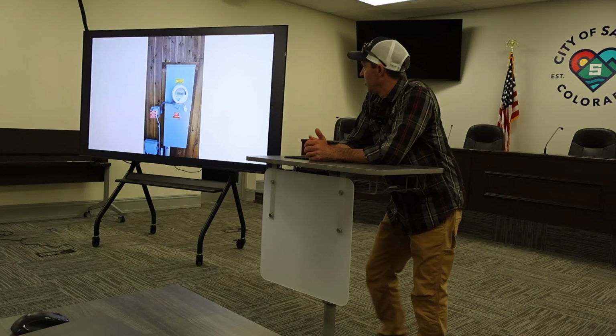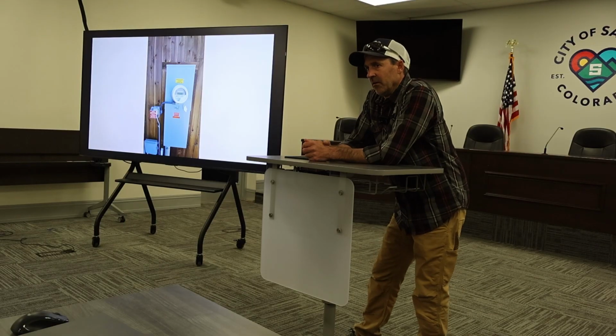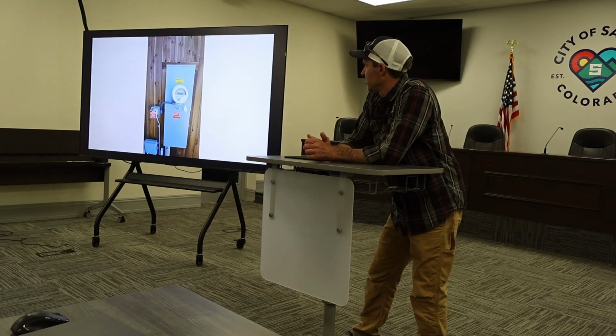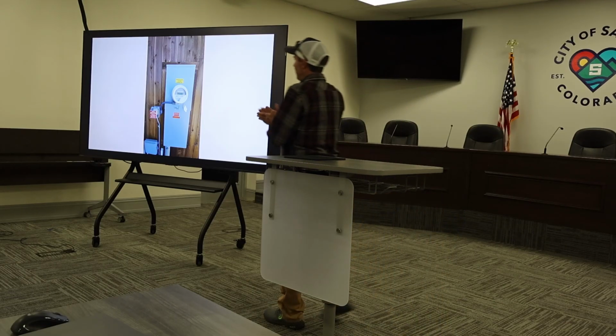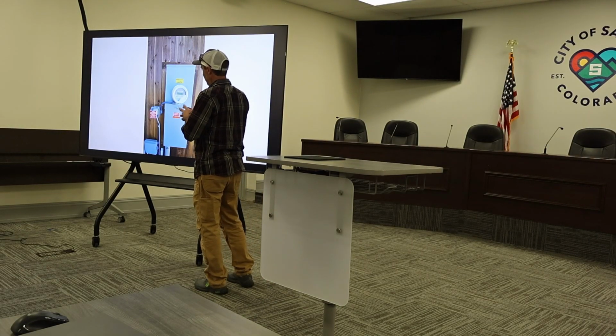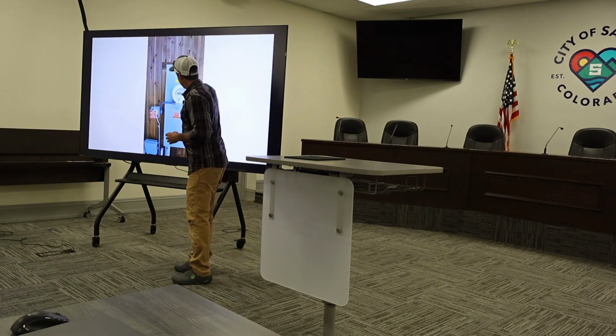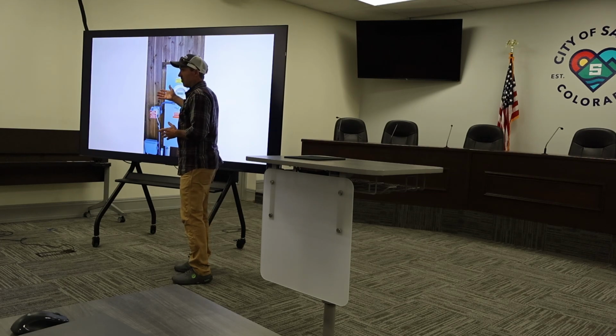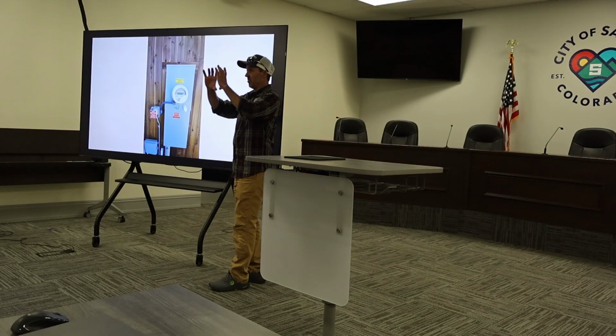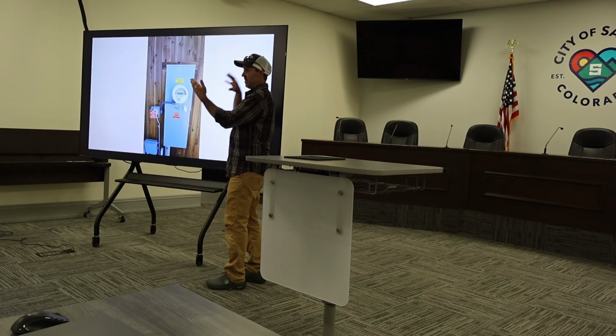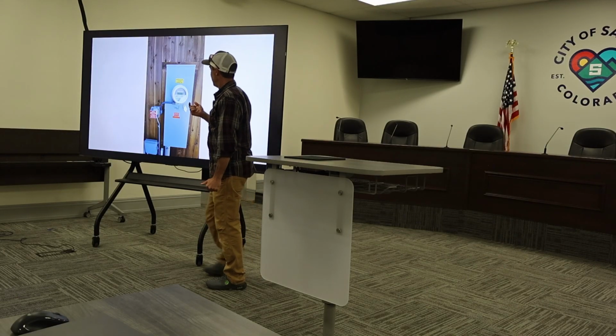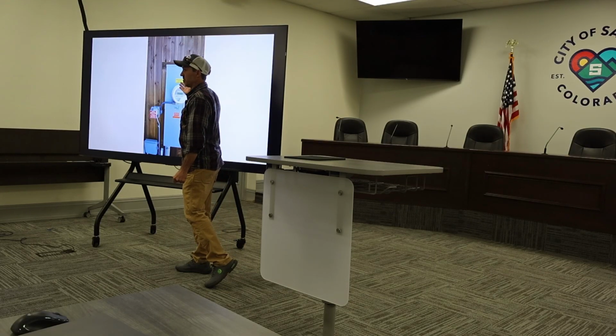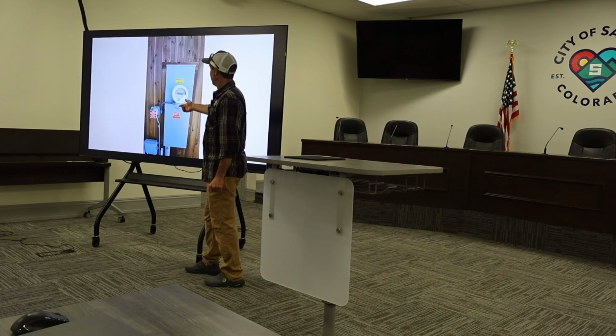This is another one - have you seen many of these, the meter collar ones? It's fairly new. This particular device we'll call a backup switch. It comes off the communication wire, in this case from a Tesla Powerwall, and there's a little collar that goes behind the meter. Xcel Energy, and most utilities, approve this. Xcel allows us, or our electrician, to pull this tag, pull the meter off, put this collar on - it's about 1.5 inches thick, that's actually the transfer switch - then the meter goes back on. In a grid outage, the collar loses power from the grid and sends a signal to the battery to kick in. It's really, really slick and easy, and you don't have to bust into panels by doing that.